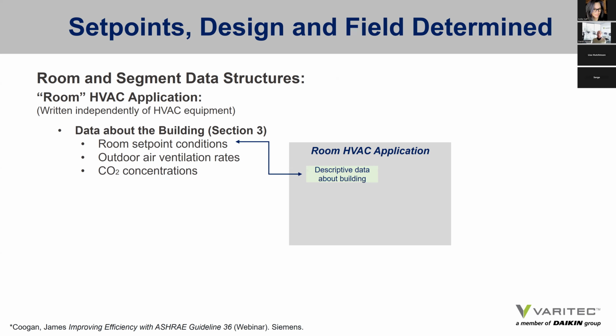And you have an HVAC application in the room. And that HVAC application has all sorts of assigned values as set points, outdoor air conditions, schedules that go on at the building energy, at the BAS, at the building automation level, or perhaps at an air handler controller, and that is actually exchanging data with the controller serving the room.